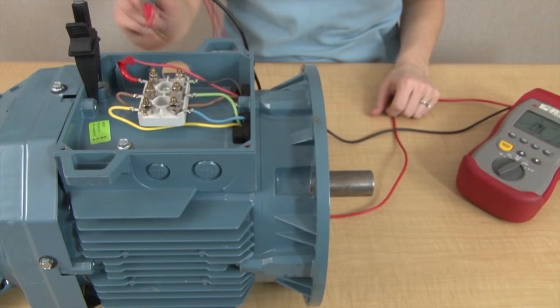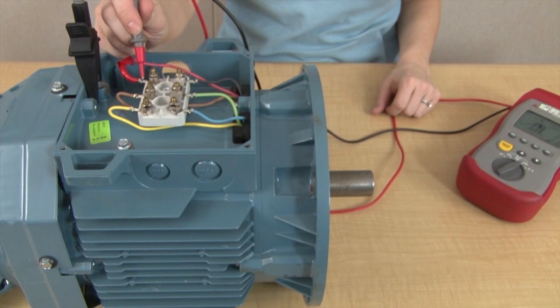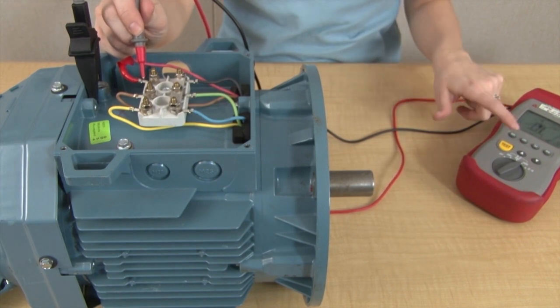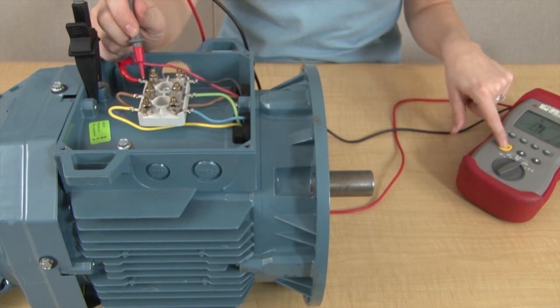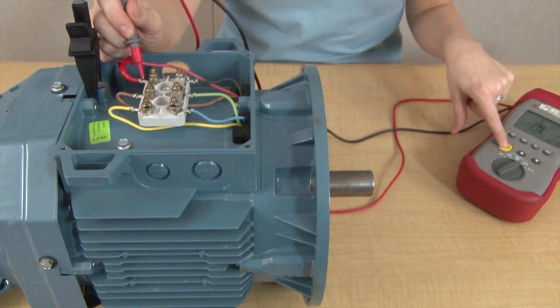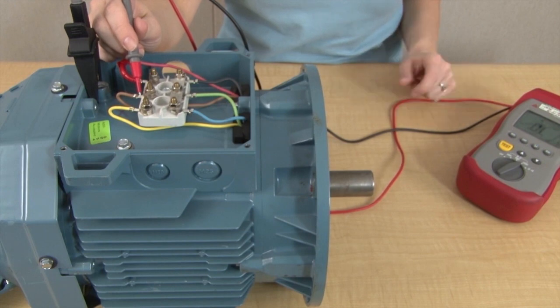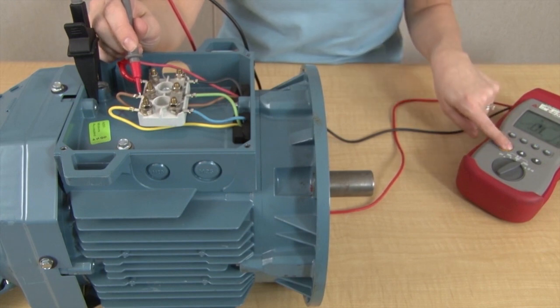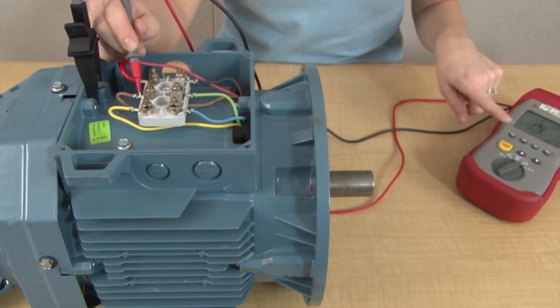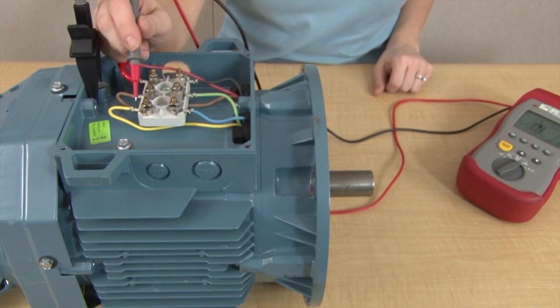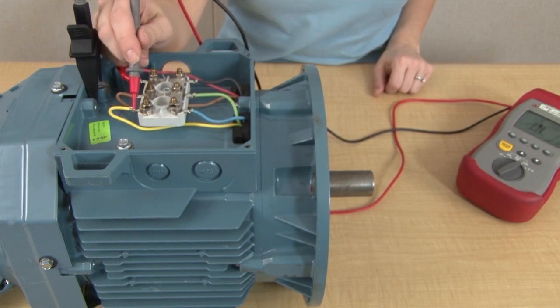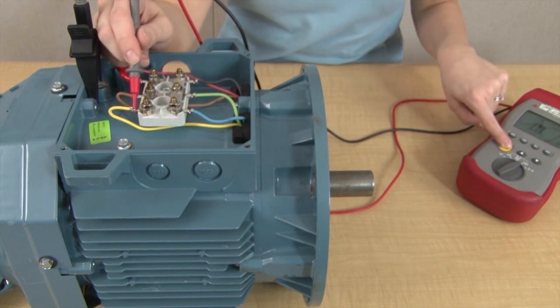First, check to see if the motor has become grounded. This is done by checking the resistance of each terminal to ground using a megohm meter, where resistance should be in the megaohms. A grounded motor will cause permanent damage to the drive.